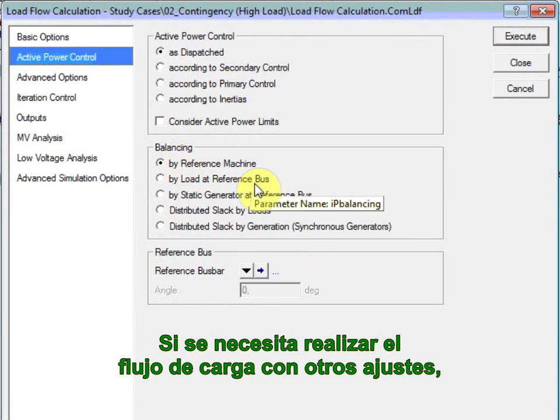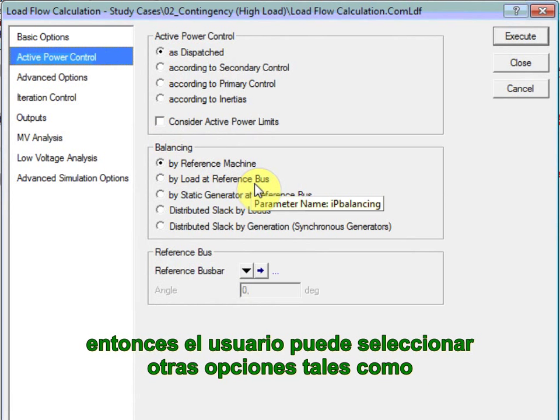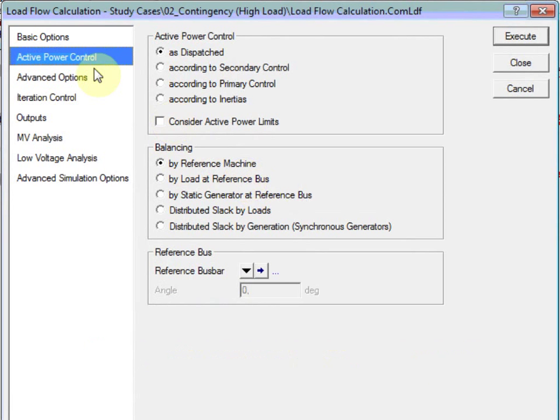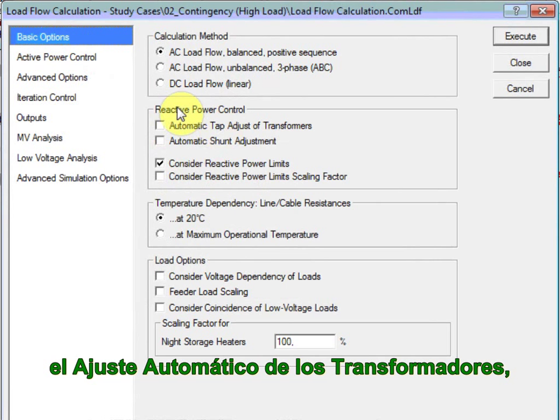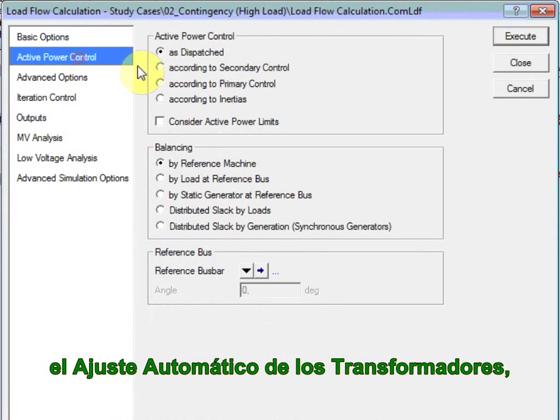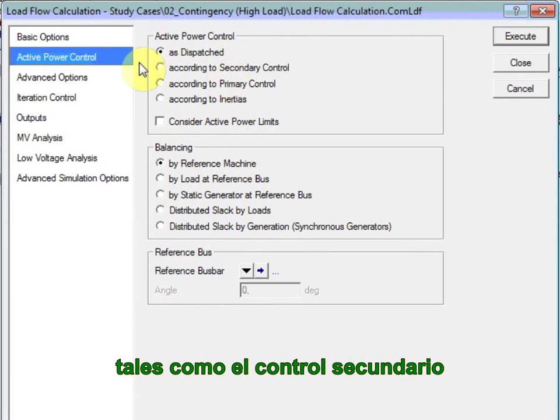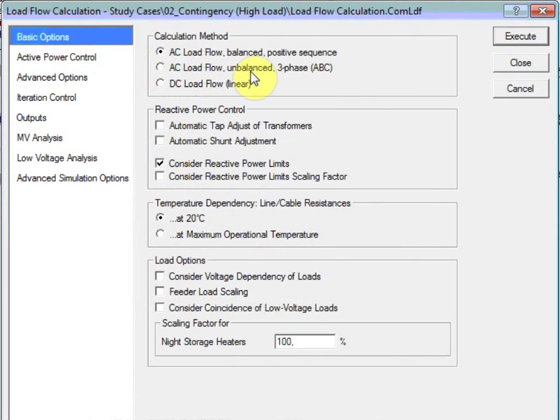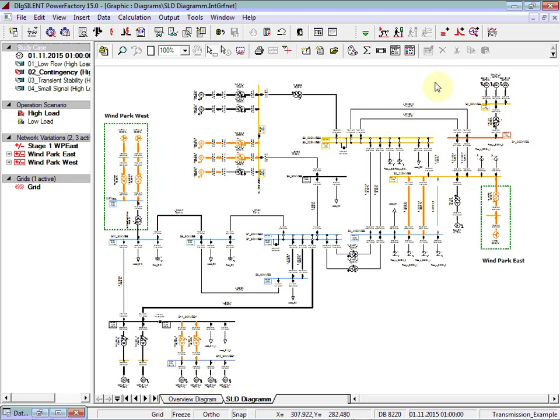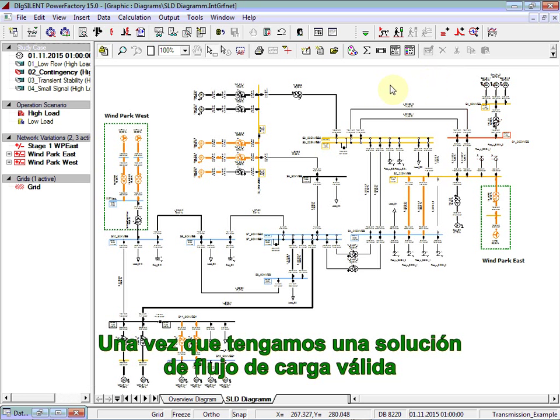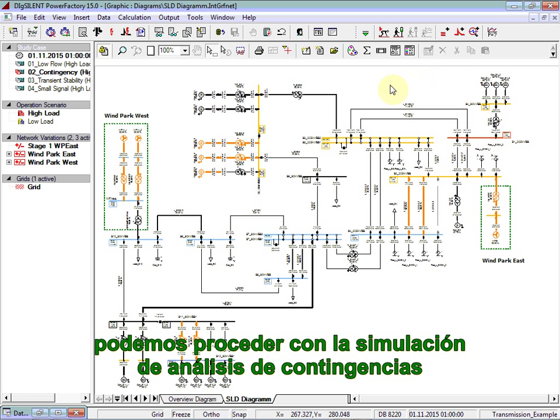If the load flow needs to be performed with other settings, then the user can select other options here, such as automatic adjustment of transformers, or selecting other active power controls such as running it according to secondary control. Once we have a valid load flow solution, we can proceed with contingency analysis simulation.